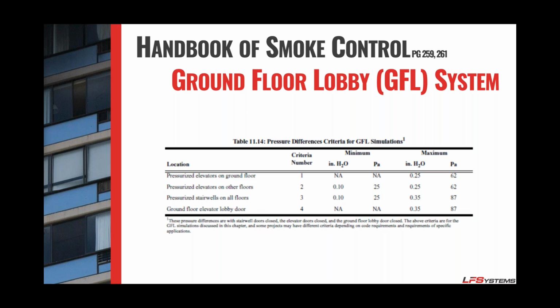If you look at the CONTAM modeling, there are 4 criteria. One, you have to make sure that your elevators on the ground floor do not exceed the max pressure. You have to make sure that you stay within range of all the other floors. You have to make sure that your stairwells maintain their pressure range. And you have to make sure that the lobby isn't overpressurized to where the doors won't stay closed.